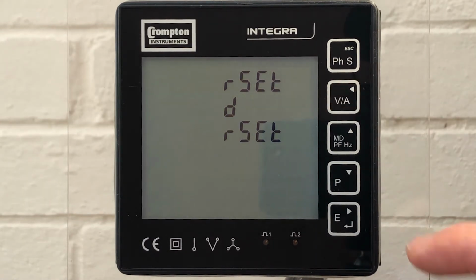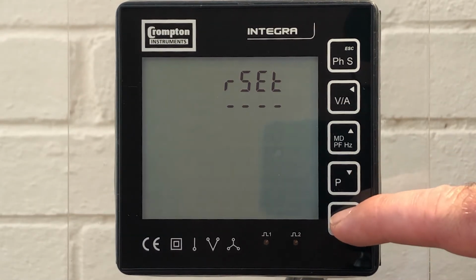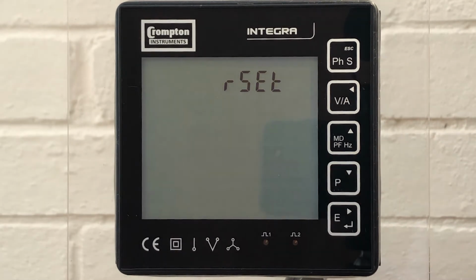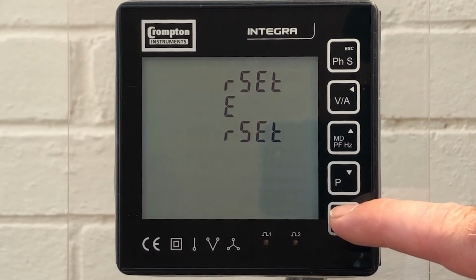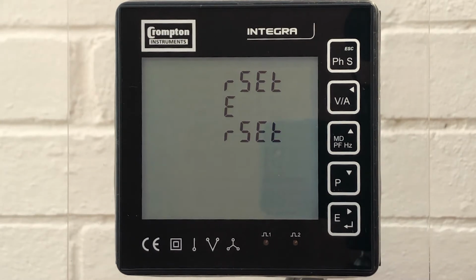And the meter will also allow for resetting energy and also demand and energy together. So if we arrow down to reset all and then arrow down to energy, we can flick through the necessary settings. If we leave it on energy and then hold E, we've now reset all the accumulated energy but left the demands in place. If we want to reset both the demands and the energy accumulated, we simply hold down E on all, and all demands and energy accumulated is reset.